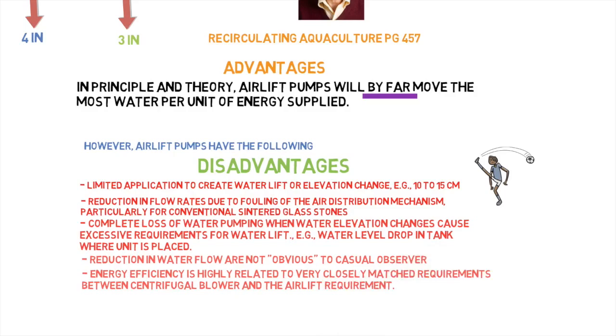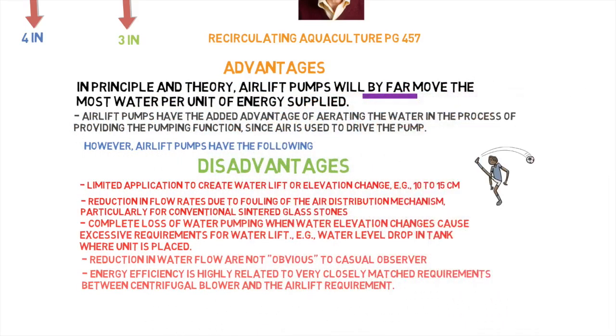Actually, there's one more pro that I've found on the next page of the book. Airlift pumps have the added advantage of aerating the water in the process of providing the pumping function since air is used to drive the pump. And this is very important. I believe this is a good pro right here as well, because if you can add aeration in there along with pumping, that's a two-in-one combo right there. And it also contributes to carbon dioxide stripping, getting rid of a lot of the carbon dioxide that builds up inside of the system.